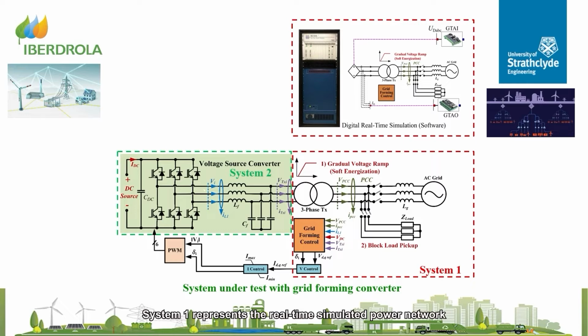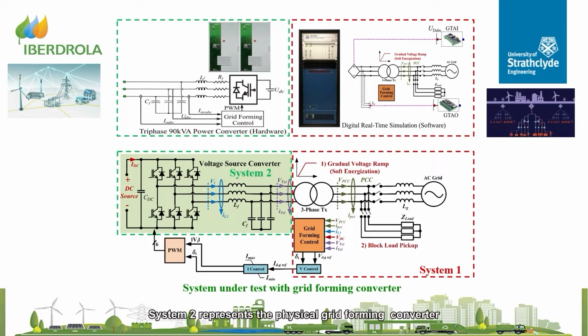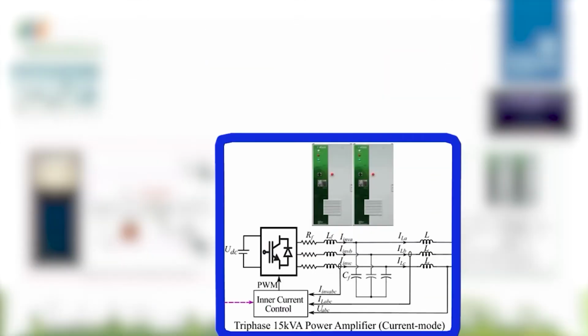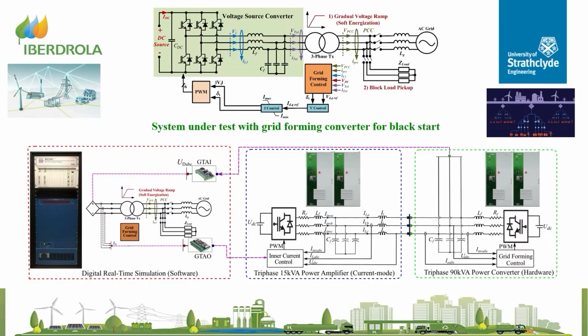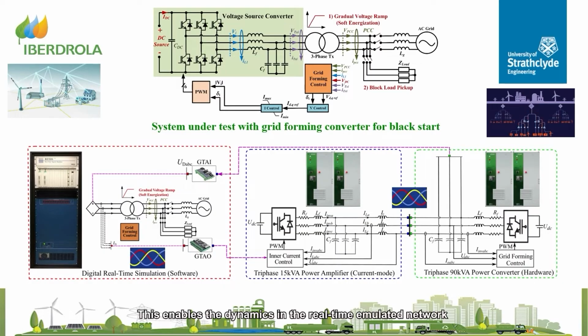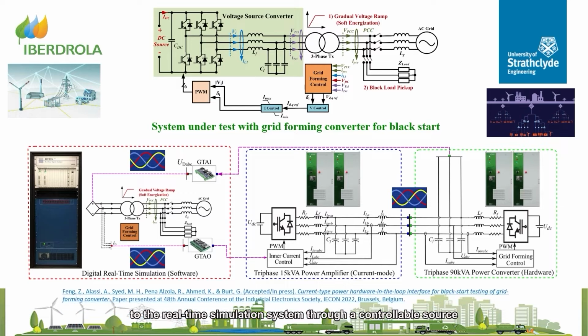System 1 represents the real-time simulated power network. System 2 represents the physical grid-forming converter. A current mode power amplifier is employed to interface these two systems by sinking or sourcing current to the converter. This enables the dynamics in the real-time emulated network to be replicated to the physical grid-forming converter. The converter output voltage is measured and transmitted to the real-time simulation system through a controllable source, thus closing the simulation loop. The detailed system modeling, scaling and time delay compensation, and stability analysis are elaborated in the referred paper script.